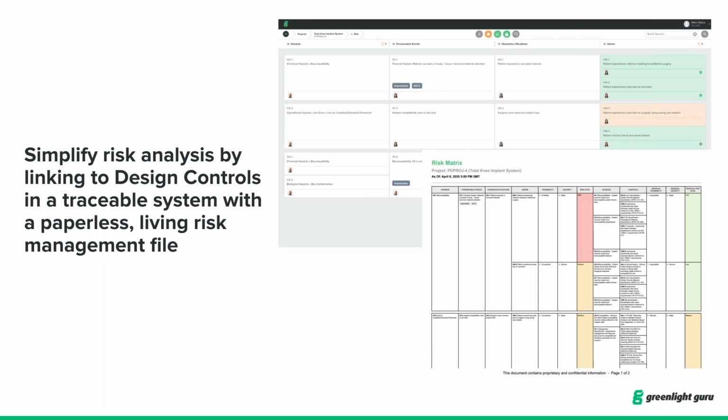These are largely viewed as separate documents and reports, but as a practical application of this, these should be ingrained with one another. You should be making risk-based decisions during your design and development process. You should be assessing the hazards, the situations, the events that lead to those situations, the possible harm, and severity and probability of those items as early as you possibly can.